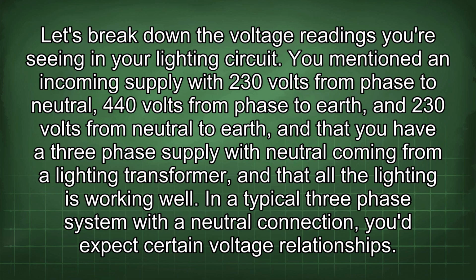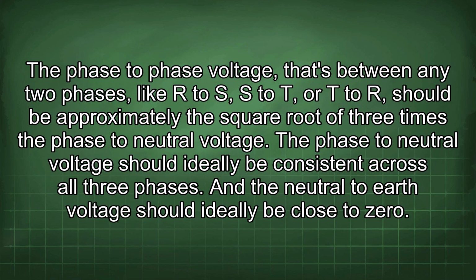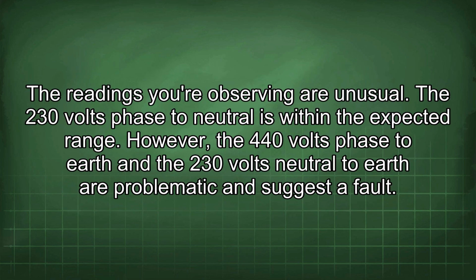In a typical three-phase system with a neutral connection, you'd expect certain voltage relationships. The phase-to-phase voltage, that's between any two phases, like R to S, S to T, or T to R, should be approximately the square root of 3 times the phase-to-neutral voltage. The phase-to-neutral voltage should ideally be consistent across all 3 phases, and the neutral-to-earth voltage should ideally be close to 0. The readings you're observing are unusual.